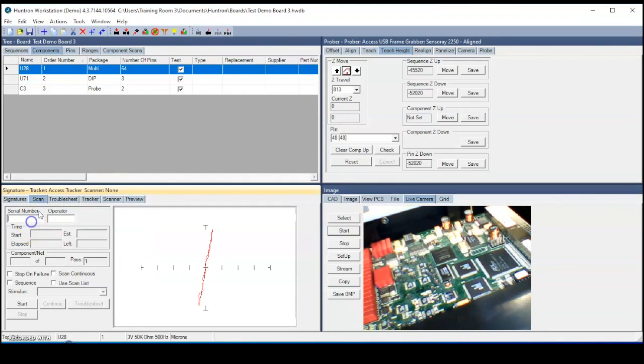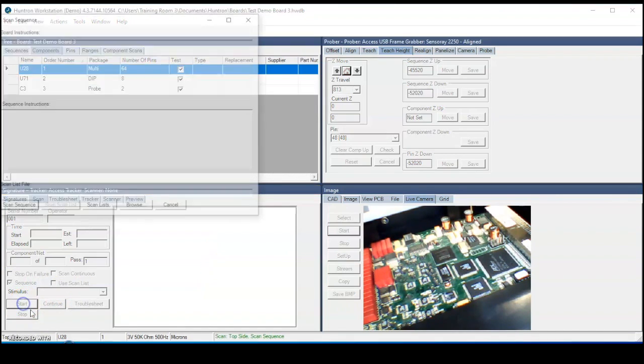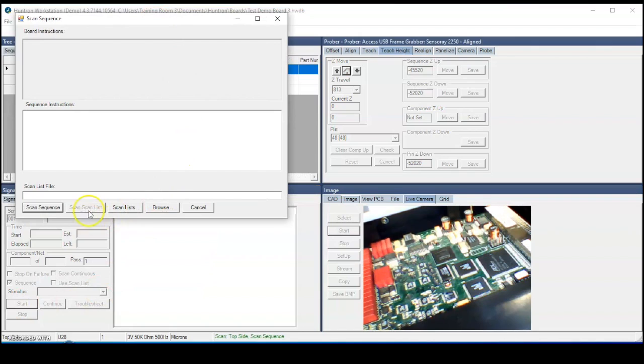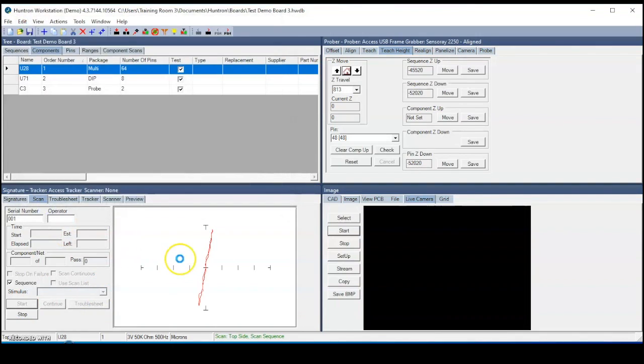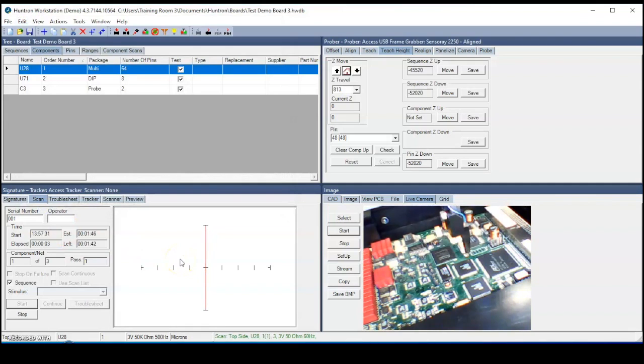Go to the Scan tab. You just have to type in the serial number. Generally, we start with a known good board first, and we want to scan a known good board, get the signatures from that to store into the database. And then click Start. It'll give me an instruction window. If I had instructions in here, it would be displayed right now. We'll click Scan Sequence and let the prober do its job.